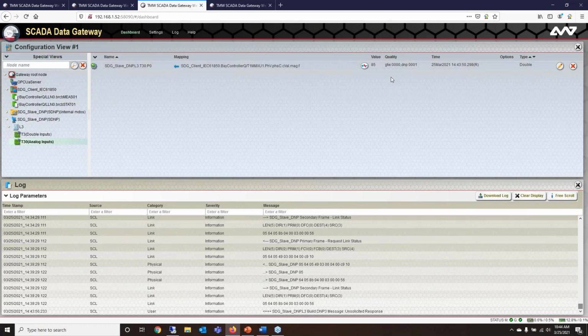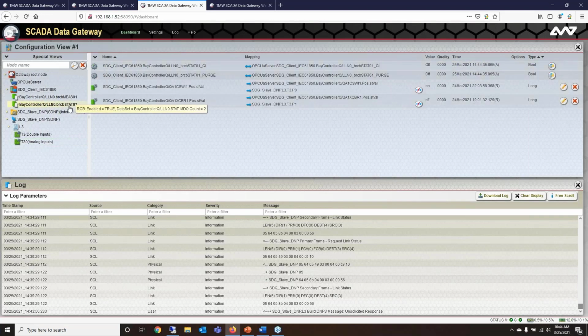I did want to point out one other thing while we were looking at the gateway tool. When I'm inside of my DNP3 outstation, you'll see that it has a mapping telling you where that value is coming from. What you may have noticed in other situations is if I went to our client, we're actually seeing multiple things, so the arrow is kind of shifted the other way. This is saying that this XCBR position is mapped not only to the DNP point that I just showed off, but it's also being mapped to our OPC UA server.